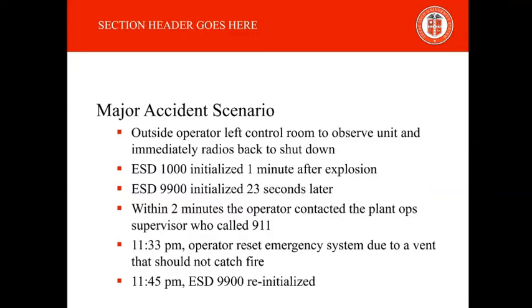The board operator initialized ESD 1000 about a minute after the explosion and initialized ESD 9900 only 23 seconds later. Within 2 minutes, the operator contacted the plant operations supervisor, who then called 911 and headed to the plant to assume the role of incident commander. After speaking with the plant supervisor, the board operator noticed a vent on top of the B-train demethanizer had caught on fire. This vent wasn't designed to catch fire, so the operator decided to reset the ESD 9900 system at 11:33 p.m. After seeing the flames go out, the operator reinitialized the ESD 9900 system at 11:45.